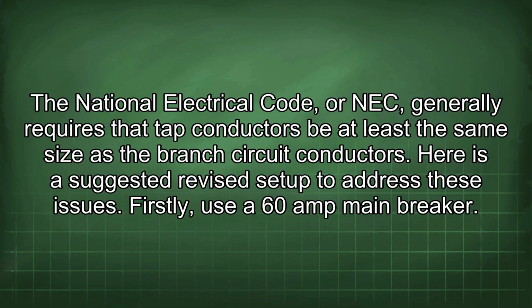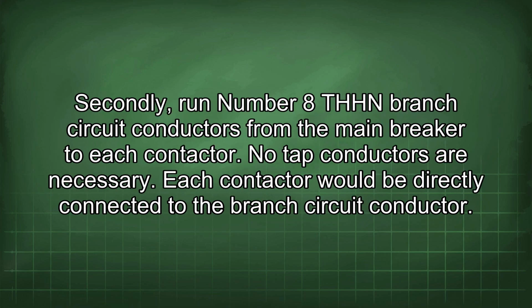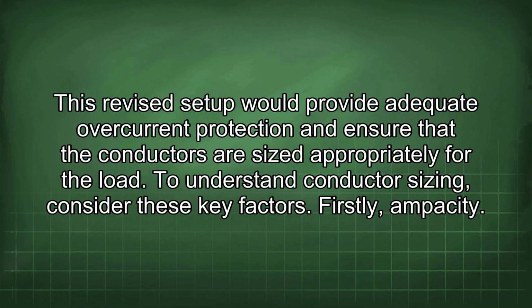The NEC generally requires that tap conductors be at least the same size as the branch circuit conductors. Here is a suggested revised setup to address these issues. Firstly, use a 60 amp main breaker. Secondly, run number 8 THHN branch circuit conductors from the main breaker to each contactor. No tap conductors are necessary. Each contactor would be directly connected to the branch circuit conductor. This revised setup would provide adequate overcurrent protection and ensure that the conductors are sized appropriately for the load.